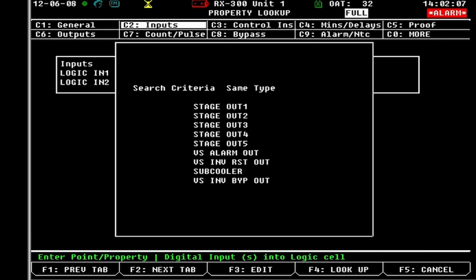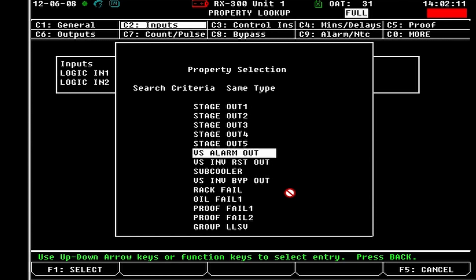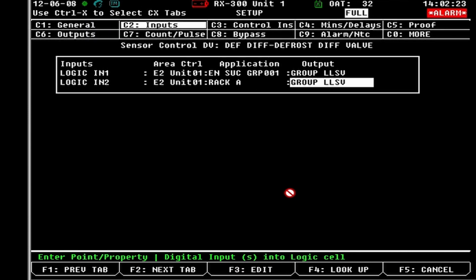So this is what I was talking about in a previous video. When you have multiple racks or suction groups on the same controller, and it's the same rack. So meaning if you have rack A, so you had a plus 23, a plus 28, and a minus 10 suction. Well, say you have multiple hot gas circuits spread out between them. Now you have the same group liquid-line solenoid for this. So in the E2, you can only control an output from one input, meaning one application can only control an output. So now you would either have to link all the cases back to one suction group in order for the defrost differential valve to turn on, or you would do a digital sensor control.